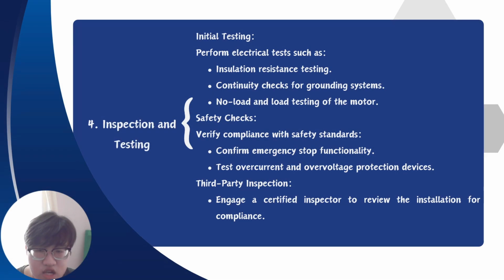Fourth, inspection and testing. Initial testing. Perform electrical tests such as insulation resistance testing, continuity check for grounding system, no load and load testing of the motor. It can prevent some short circuits in the wiring. Next, safety checks. Verify compliance with safety standards. Confirm emergency stop functionality. Test overcurrent and overvoltage protection devices.